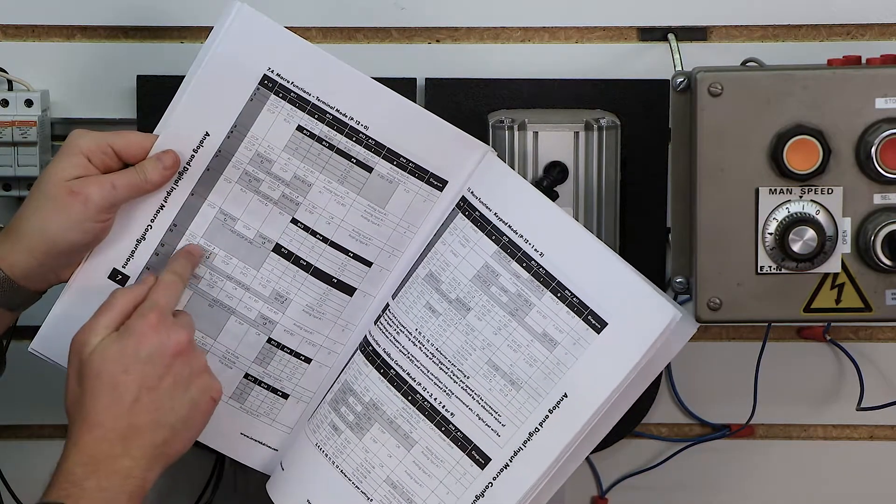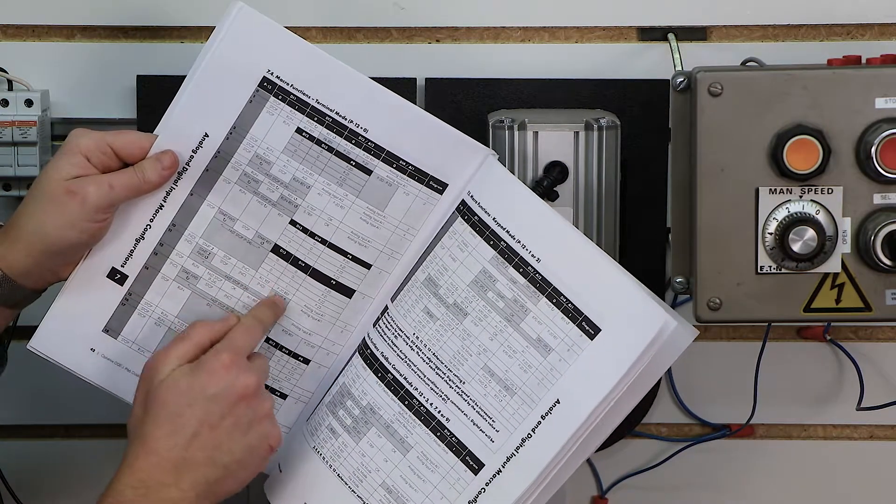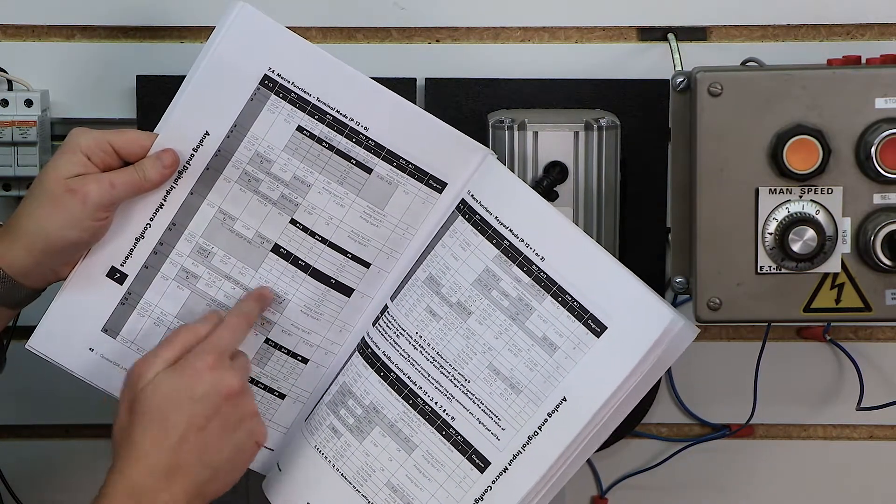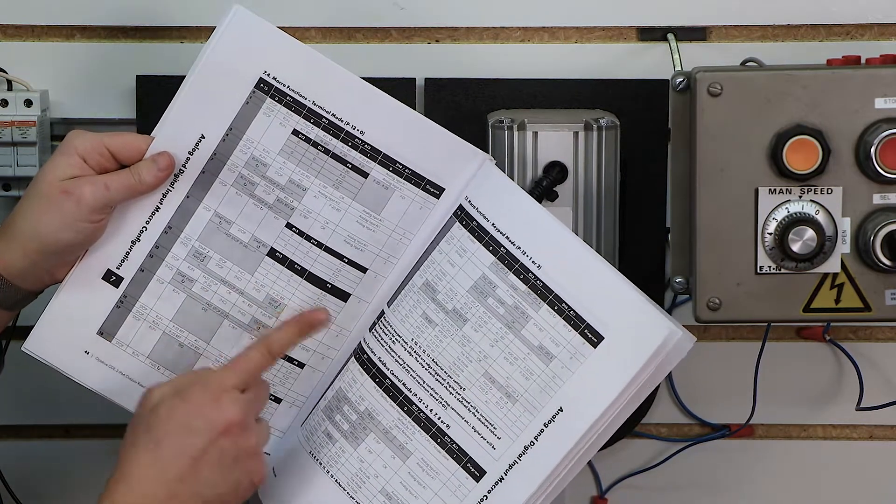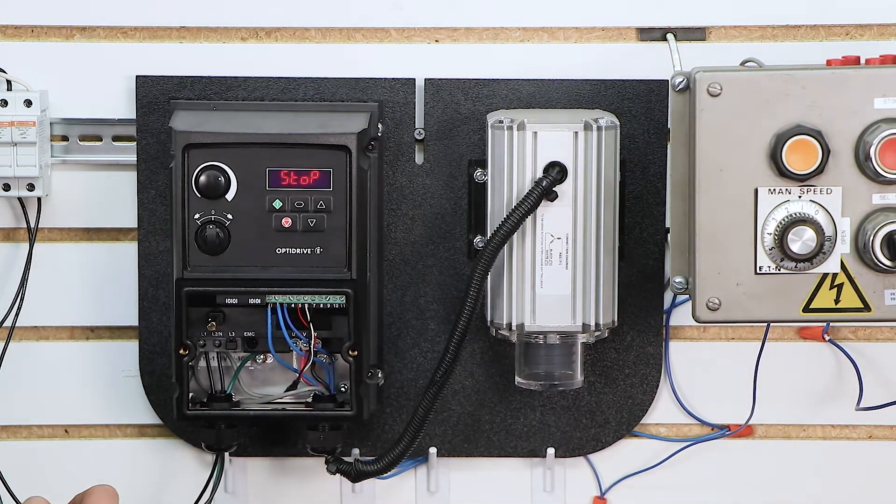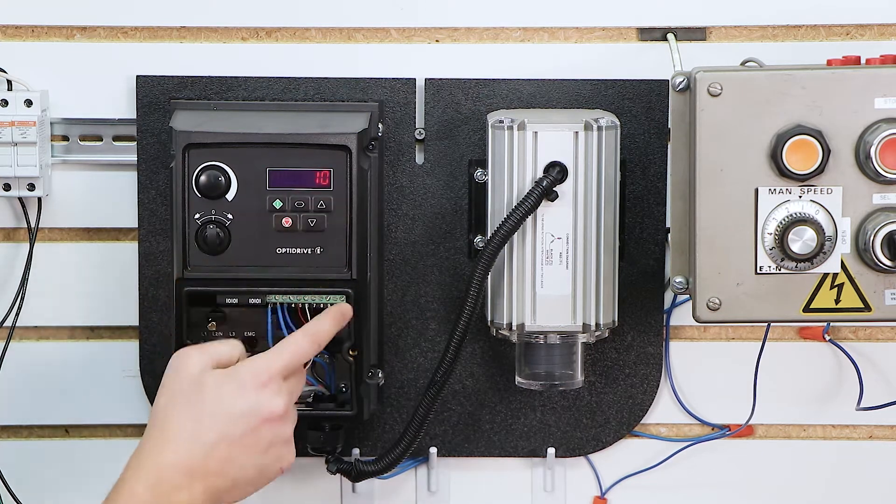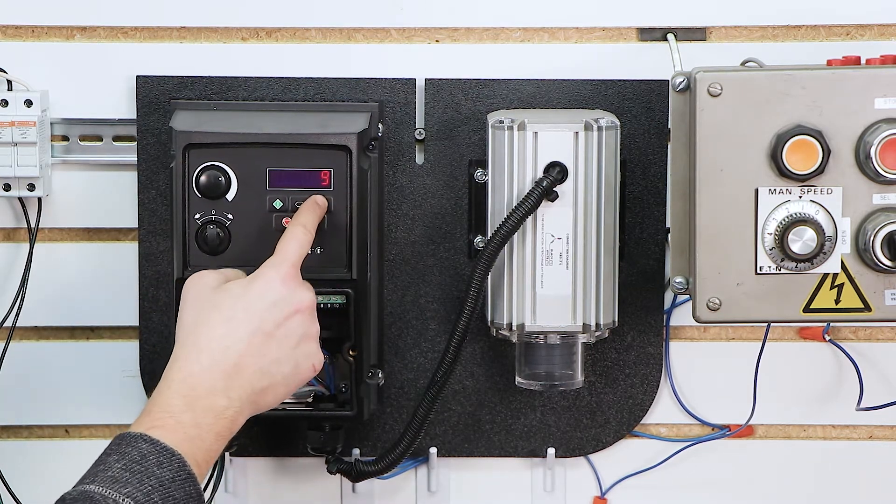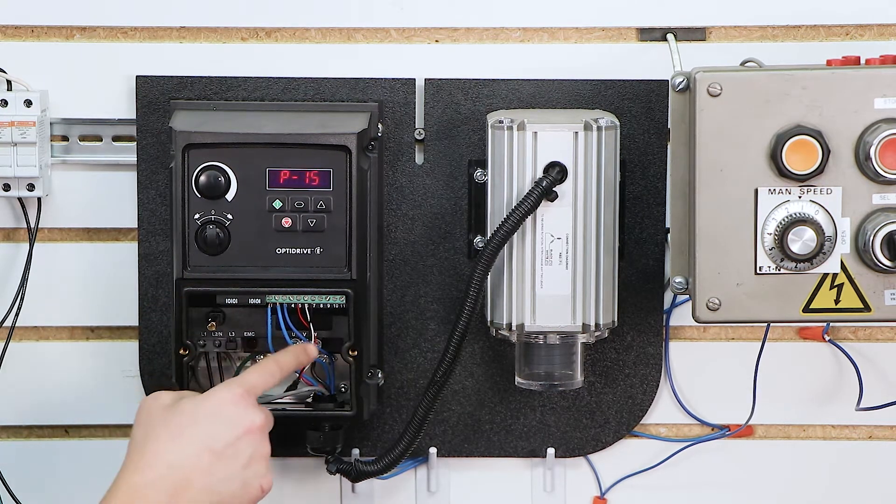So digital input 1 is going to be our start. Digital input 2 is going to be our stop. Digital input 3 is going to let us choose our speed reference. In this case, we're just going to leave it open, and it's going to default to analog input 1, which is what we wired these to. You'll see that here in a second. So let's go ahead and go to P15, select the menu again. I've already got it set to 10. You can scroll through these, and that sets up my programming for the digital inputs. Now let's get to the wiring.